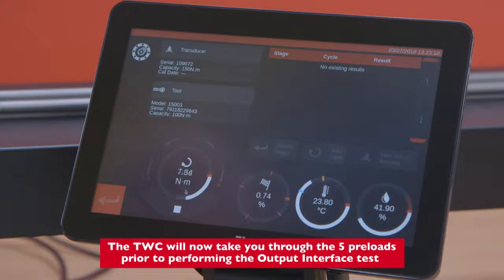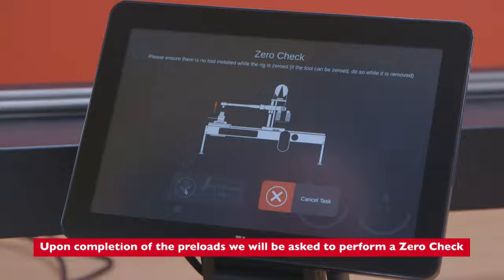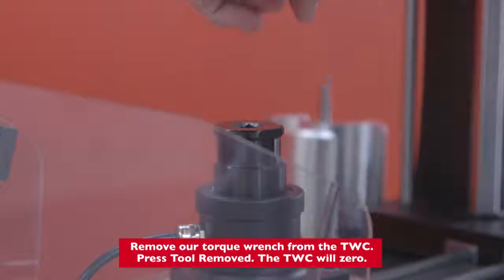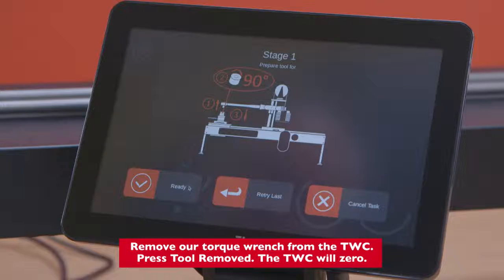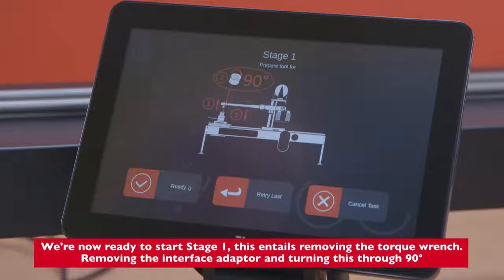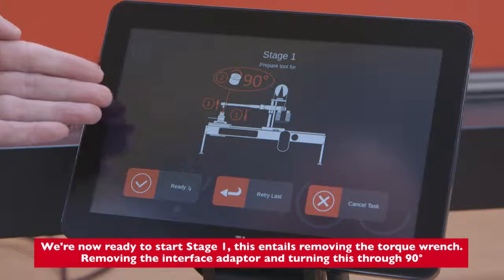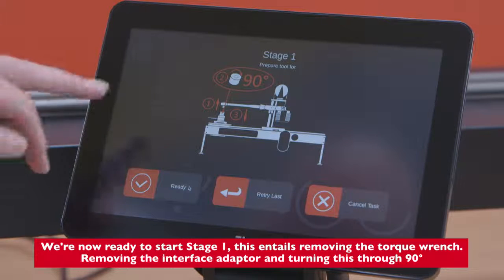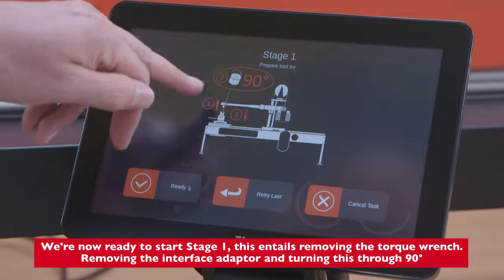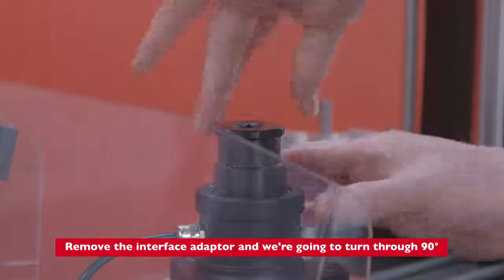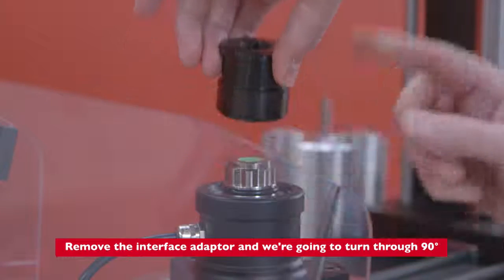The TWC will now take you through the 5 preloads prior to performing the output interface test. Upon completion of the preloads, we would be asked to perform a zero check. Remove our torque wrench from the TWC, press tool removed, the TWC will zero. We're now ready to start stage 1. This entails removing the torque wrench, removing the interface adapter and turning this through 90 degrees. Remove the interface adapter and we're going to turn through 90 degrees.